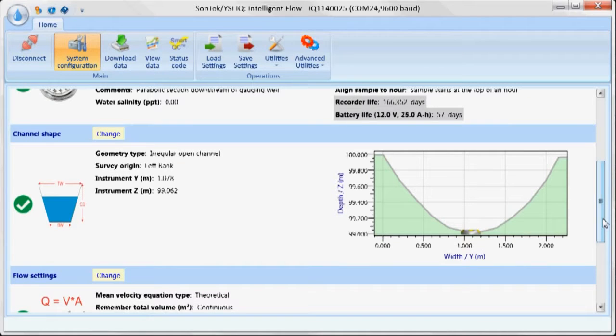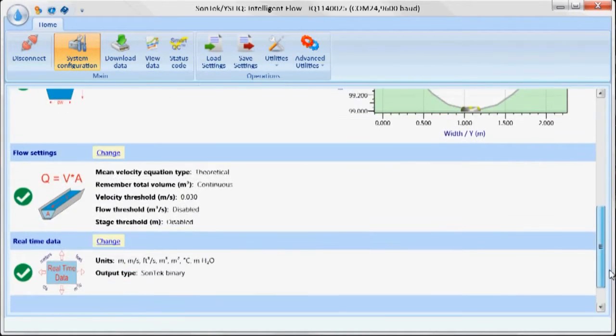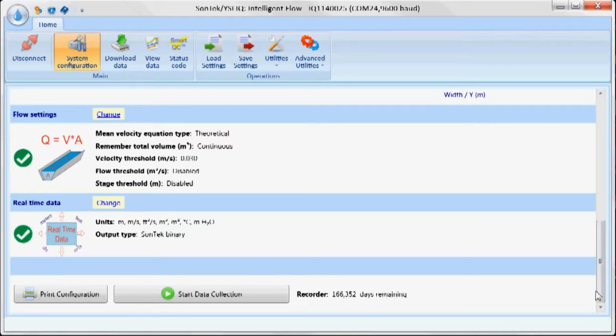Next, I'm going to program the instrument on how to do the flow calculation. There are two basic calculations. One is theoretical, which in most cases you'll be using—it doesn't require a calibration or a velocity index. The second, if you're in a natural, possibly large, river or some unique flow setting, you may want to develop your own discharge rating. In that case, there's a velocity index setting.